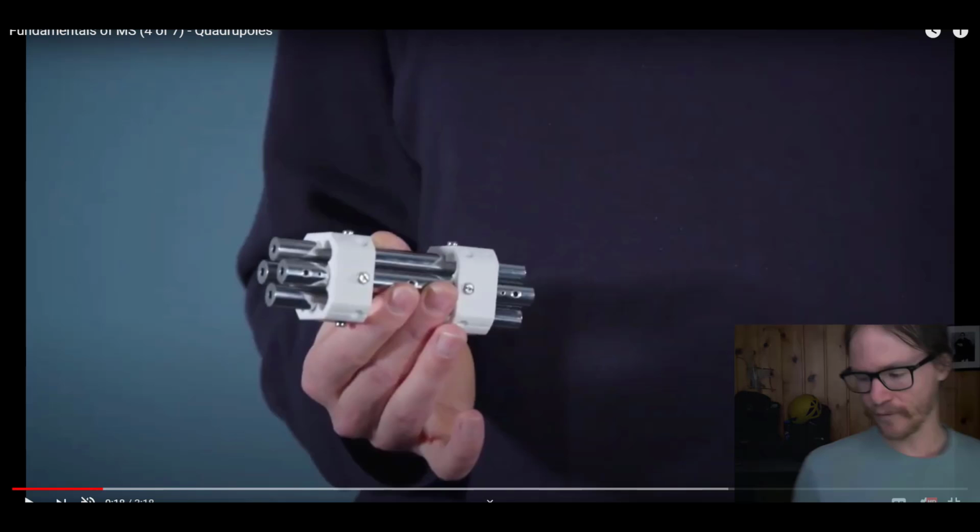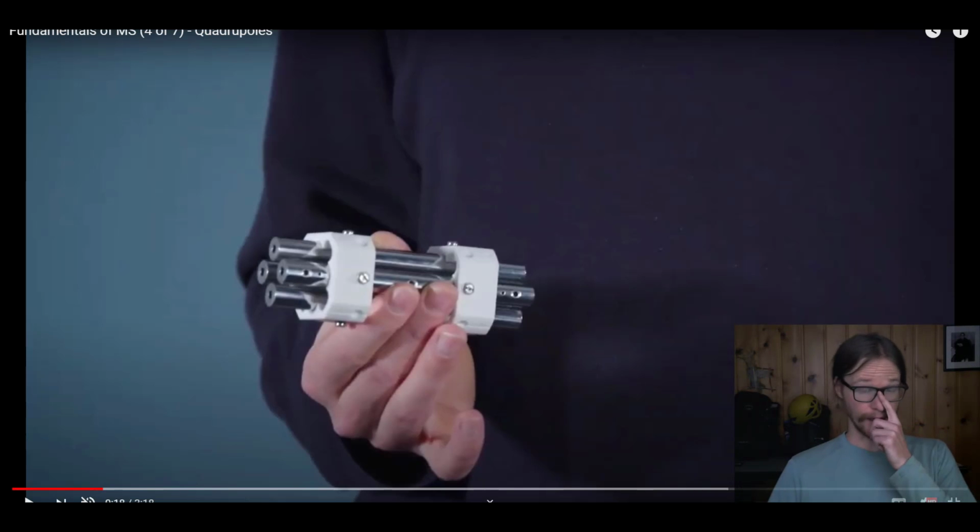So we're going to start off with the Quadrupole, and as I mentioned, we've got lots of these on campus. It's pretty small. So this is actually a version of the Waters Quadrupole. We have a Waters Quadrupole on our LCMS. And it looks like this. It's about the size of a human fist, and you can see the origin of its name. You have the four rods or the four poles.